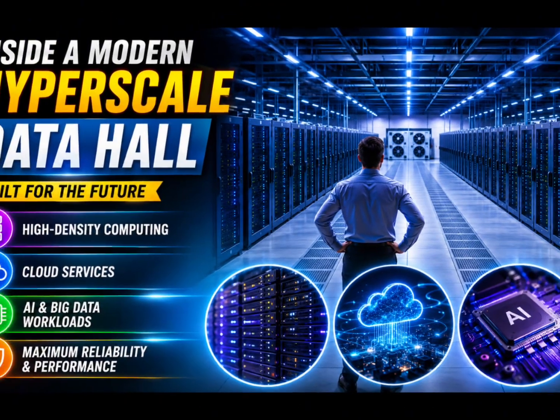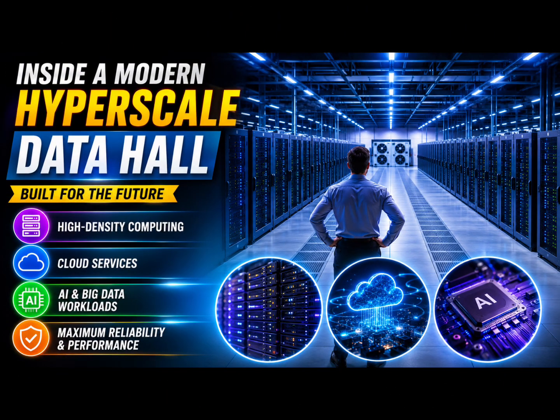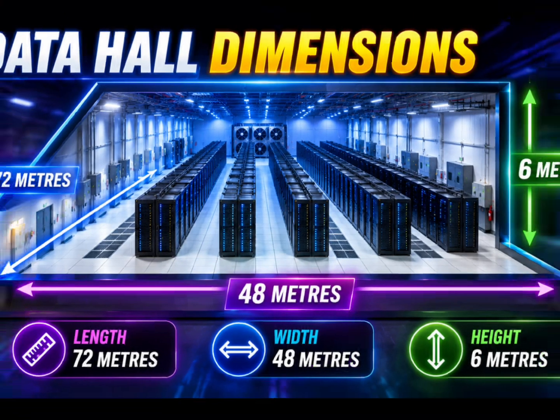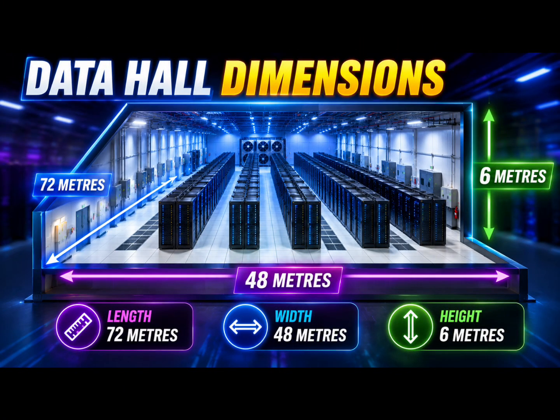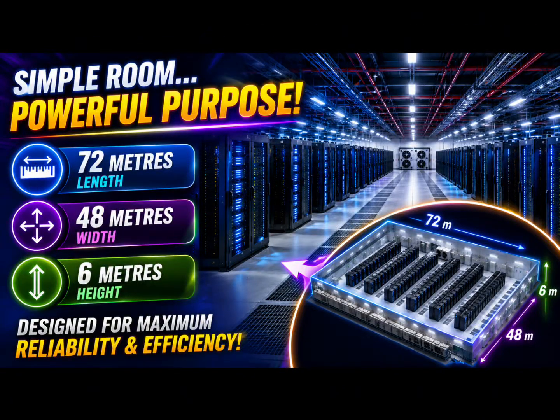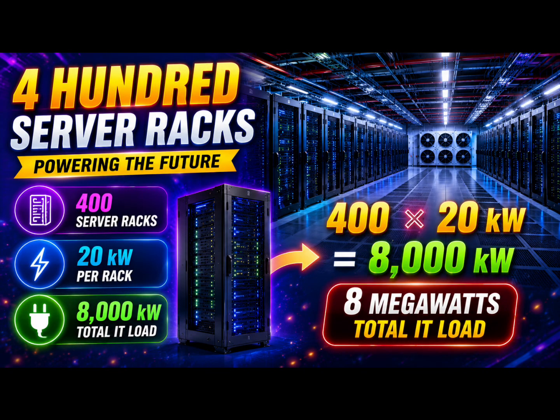This is a modern, hyperscale data hall designed to support high-density computing, cloud services, and the rapidly growing demands of artificial intelligence. The room itself is surprisingly simple. 72 meters long, 48 meters wide, 6 meters high. But don't let the empty space fool you. Every square meter has been carefully planned to maximize reliability, airflow, and cooling efficiency. Inside the room, there are 400 server racks. Each rack consumes 20 kilowatts of electrical power.